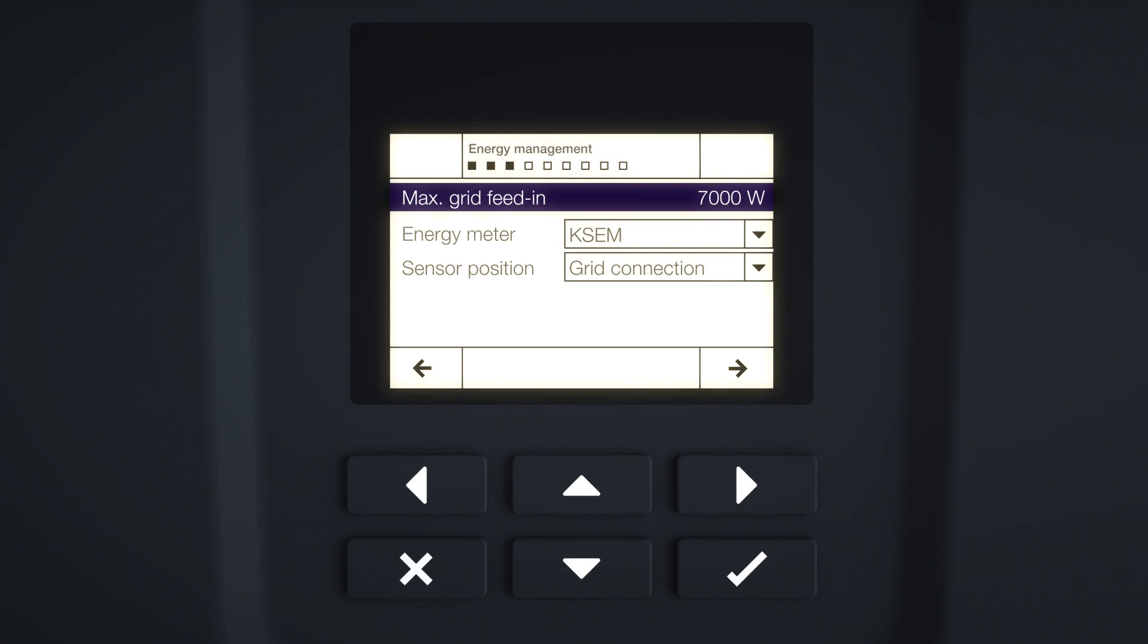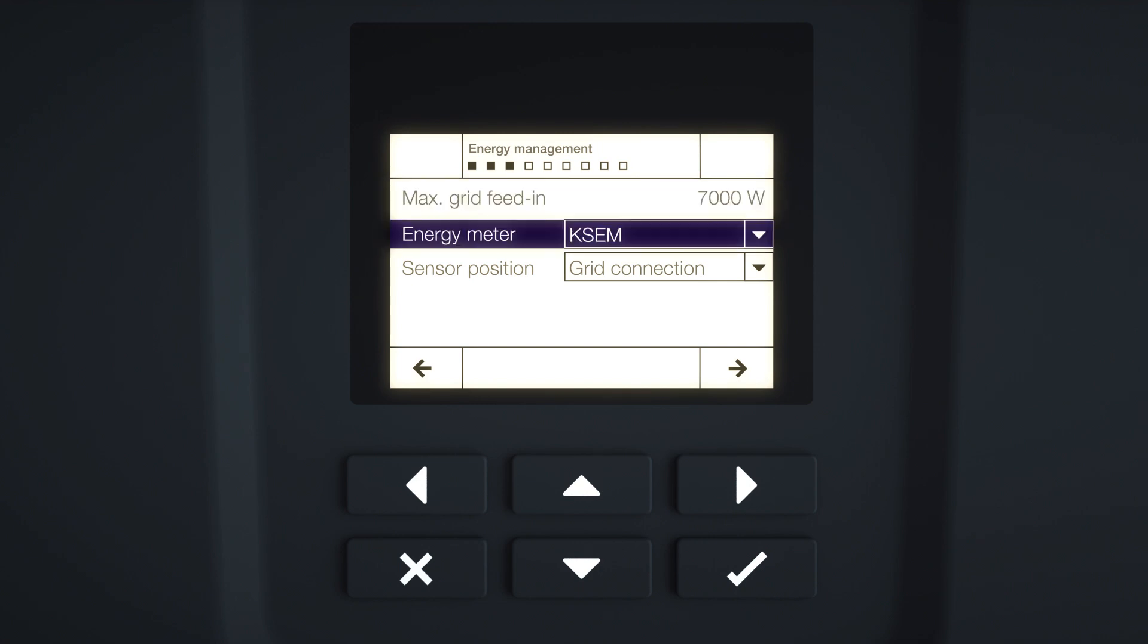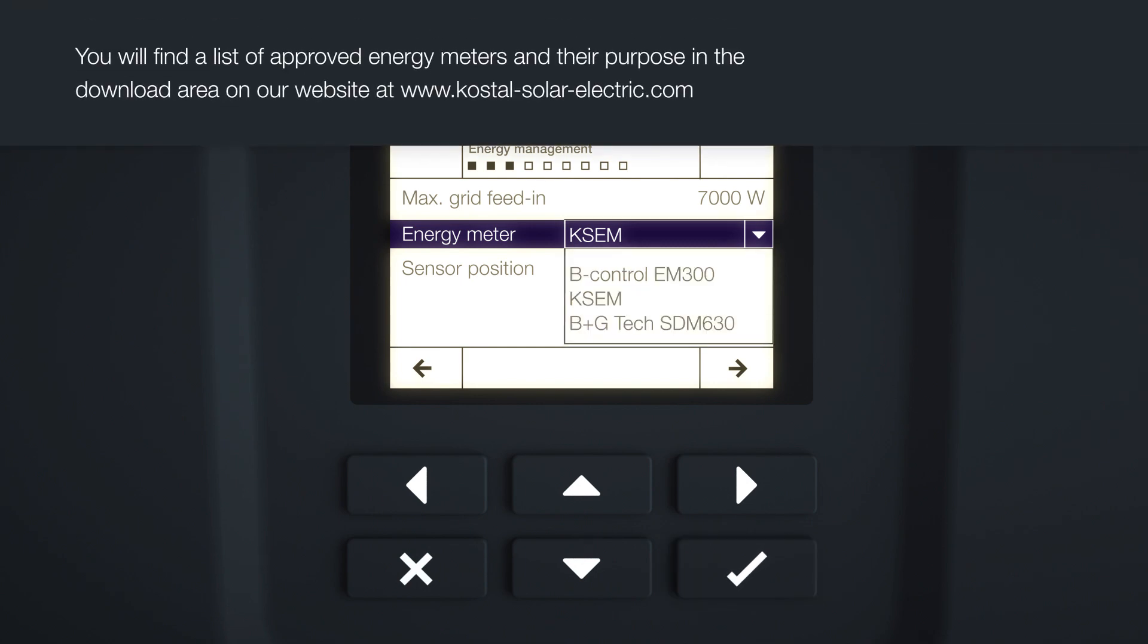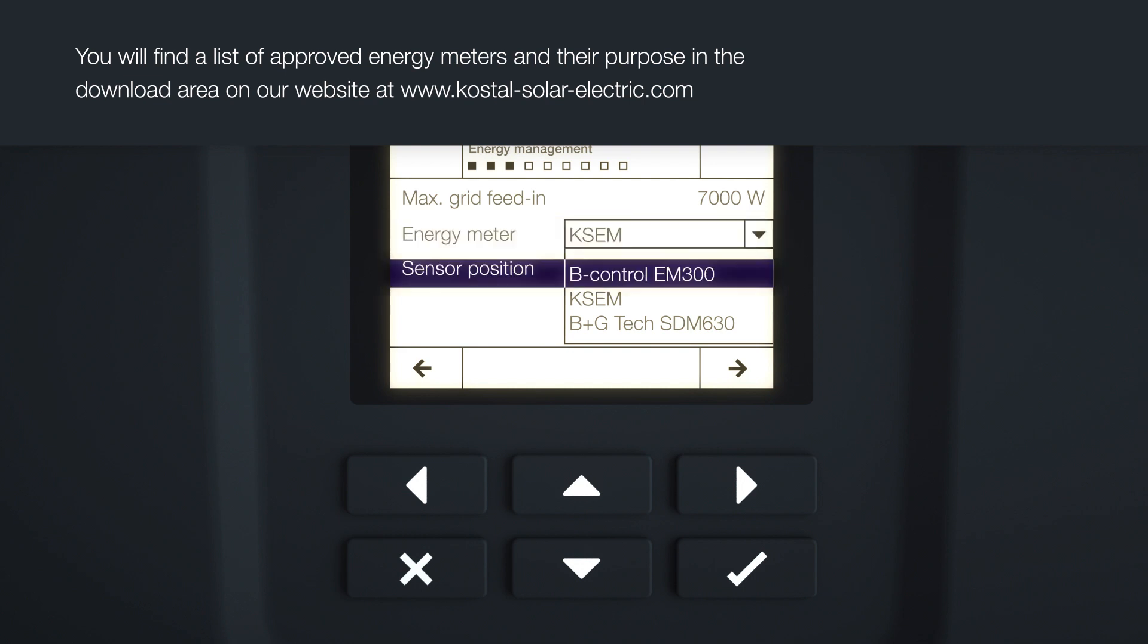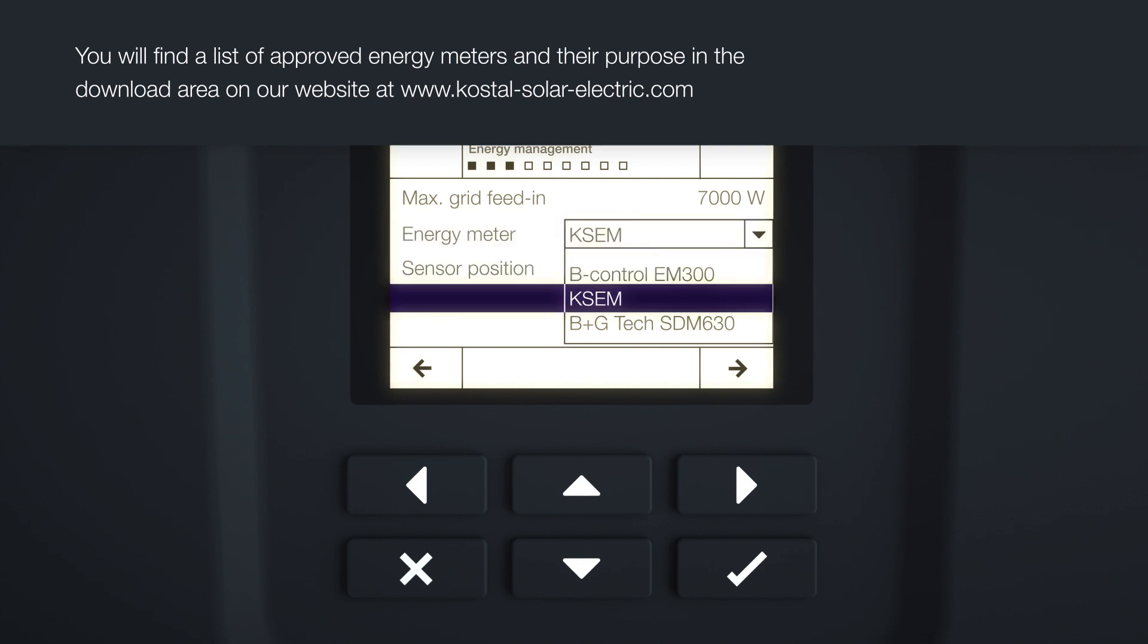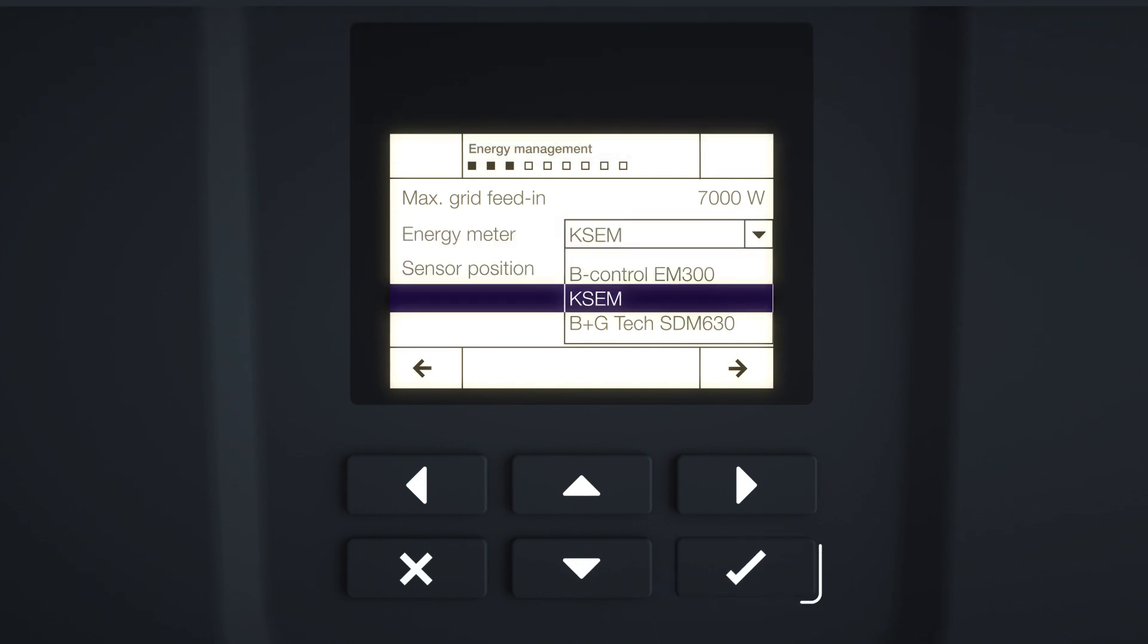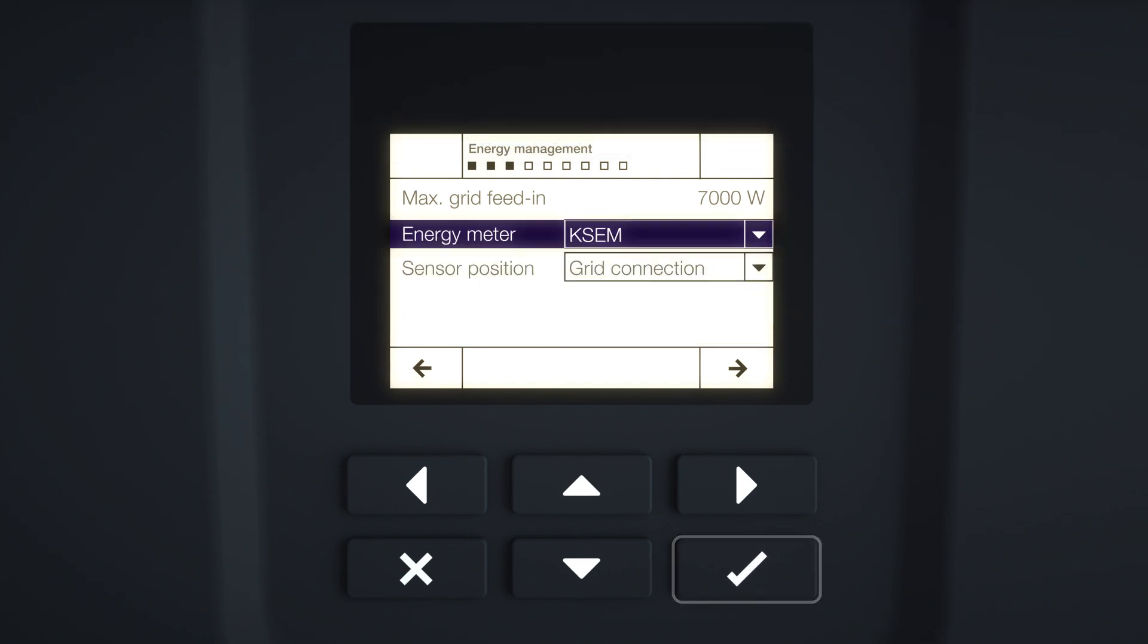Use the arrow keys to select the energy meter field and press Enter. Now you can select the energy meter fitted from the list and confirm with Enter. To run a battery on the PlentiCore Plus and the PlentiCore BI, you will need to use an energy meter.